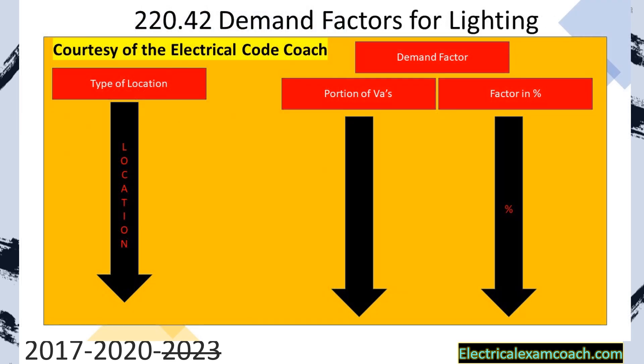When we get to table 220.42, we always read the black bold heading to make sure that we're in the right table and it says demand factors for lighting. Now you can ask the question if this is the three VAs per square foot — well, it includes receptacles, and you are correct. We are allowed to use this table for commercial lighting or any of the lighting in the following locations that we're getting ready to talk about.